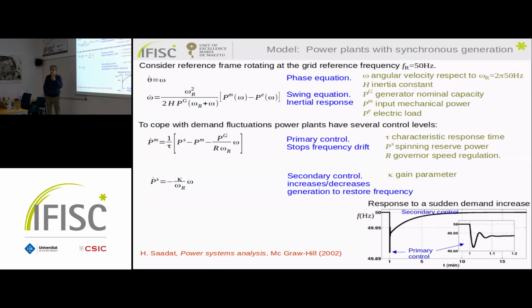Now the primary control only operates if the frequency is not the reference frequency. By the way, I've changed the notation in this transparency. Now omega here is the deviation from the reference frequency, and omega-ref is the reference frequency — so this is the frequency deviation with respect to the reference. So it only applies Pm if the frequency is not at reference, if it's not zero.